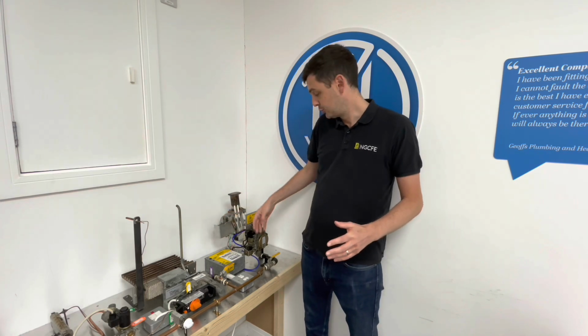The fan kicks in, draws gas through the air gas ratio valve, as well as air, premixes it, and sends it to the burner. Once it gets to the burner, it's ignited by the ignition probes. The voltage that's present at the rectification probe then converts from AC to DC by travelling through the flame and makes its way back to the board. Once the board senses that there's DC current there, it knows there's a flame there and stops trying to ignite and then moves on to the next part of the sequence, i.e. allowing more gas through to the main burner, or ramping up, whatever the next stage may be, as relevant to which boiler the unit's on.